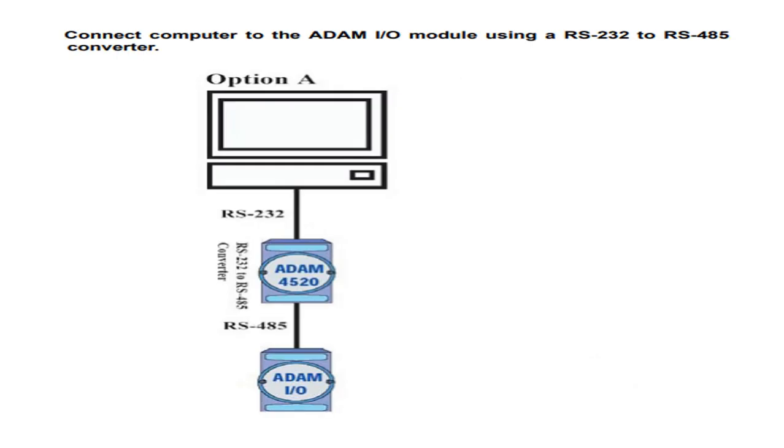Now, looking at the screen, you need to build the RS485 network starting from an RS232 network. This is because computers have RS232 ports or USB to RS232 ports. From there you need to put an RS232 to 485 converter. That is where you begin the RS485 network. So that way there is no escape from RS232 even here.